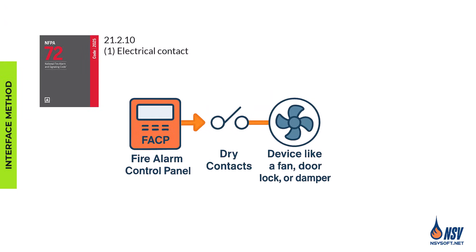There are three interface methods. First method is dry contact relays. This is the most traditional and common method. The fire alarm control panel uses a simple electrical connection to open or close a circuit in the connected system, providing a basic on-off or open-closed signal.